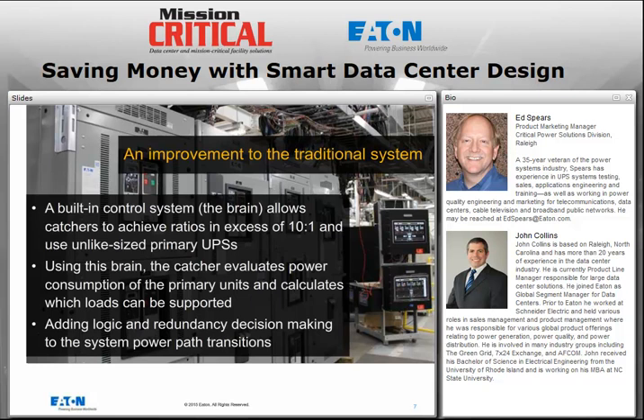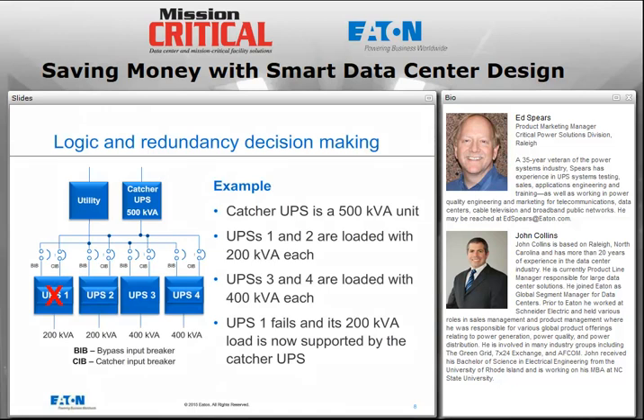So there's a lot more flexibility here, where a problem with the UPS doesn't result in that UPS grabbing and basically taking away the catcher from the rest of the UPSs. There's some sharing that can be done. And by adding logic and redundancy to this decision-making process, we get some variable power path transitions and some automatic operation that takes the right action no matter what type of failure occurs. So let's look at the next slide and see what this type of system might look like.